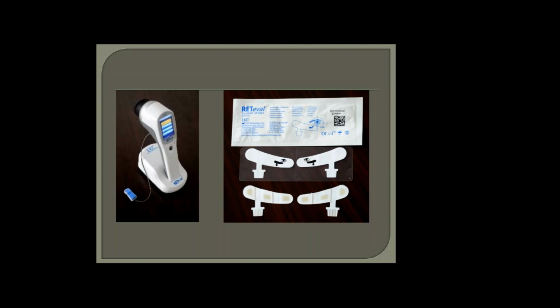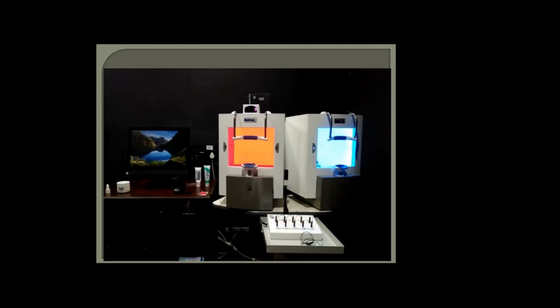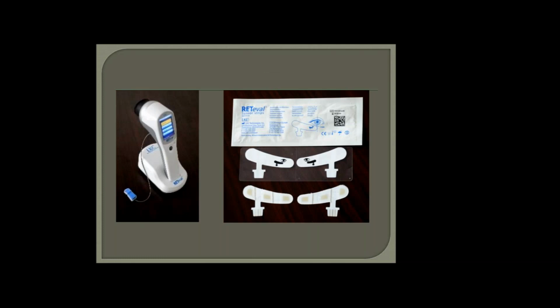As I have discussed in my previous slides, these models are all tabletop models. So it is not possible to perform the test if a patient is in the supine position, in the operating theater, not cooperative, or in the pediatric age group. At that time we should use some advanced technology. We also have a portable instrument that can be used on a daily basis, and this machine is applicable in the scenarios I have just discussed.